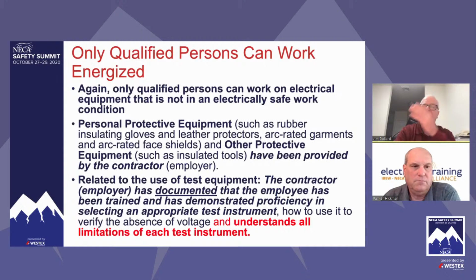But a very key piece there, Palmer, is the limitations of the test instrument, right? Yeah, so when we talk about the limitations of the test equipment, we hopefully think about voltage for sure. How many times have we seen someone stick a 600 volt or 1,000 volt tester on a 5 kV branch circuit? They're working on a chiller or a neon light transformer. So certainly that. But category rating is probably the next frontier.